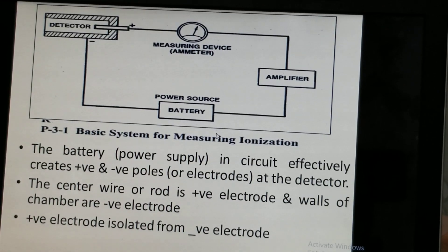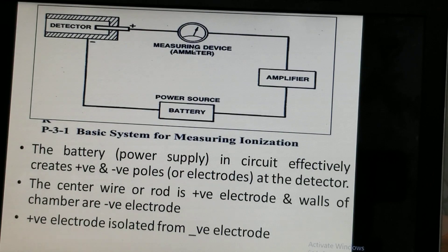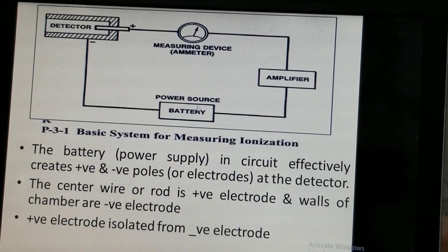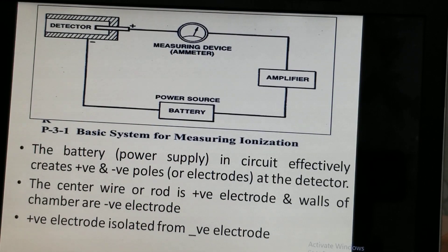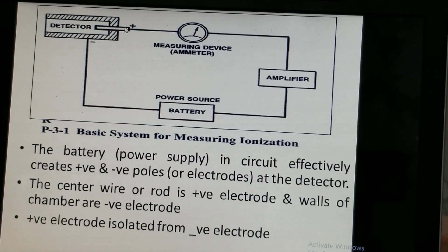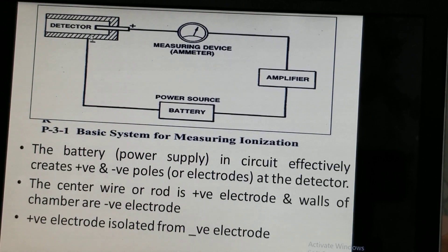This detector system measures ionization. It has a detector, a measuring device called an ammeter, a signal amplifier, and a battery or power source. The battery creates positive and negative poles at the electrodes in the detector. The negative side of the battery is connected to the negative pole, and the positive side is connected to the positive electrode — called the anode — which is the central wire. The chamber walls are the negative electrode, and the positive electrode is isolated from it.